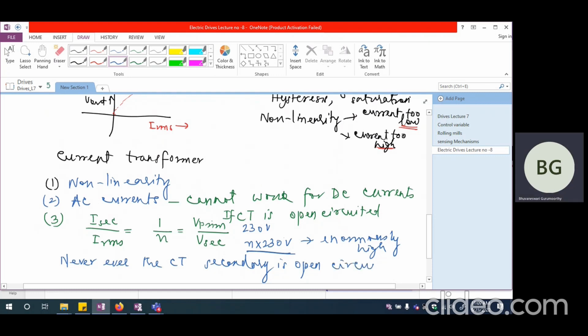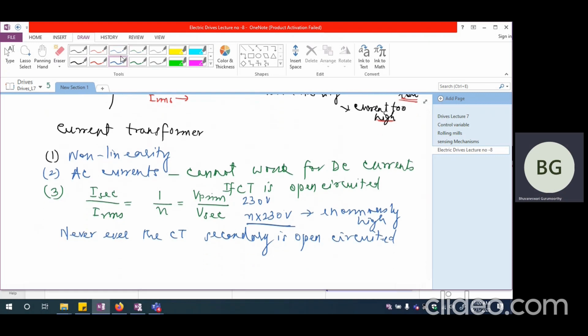So what we connect as the resistance across the current transformer should be really, really a small resistance. What do we mean by a small resistance? It depends upon whatever is the R equivalent of the current transformer, which we can find out by conducting an open circuit test and a short circuit test. So whatever R equivalent we find out, compared to that, the resistance I am connecting across the transformer should be smaller. So this R equivalent has to be much greater than the resistance connected across the current transformer.